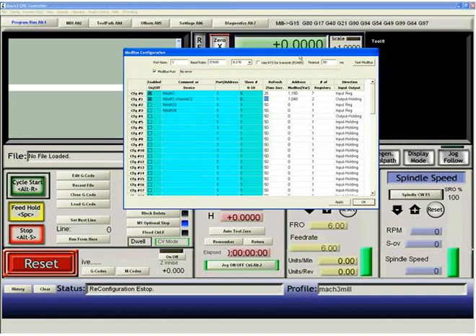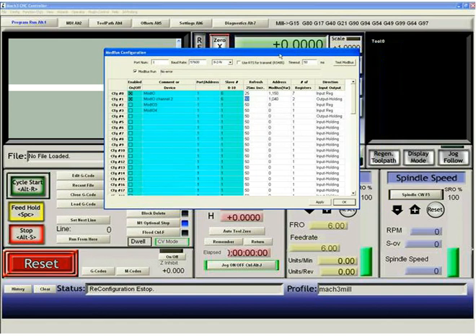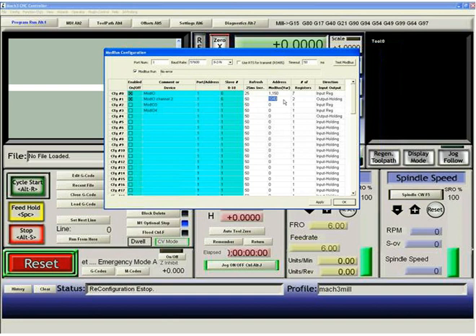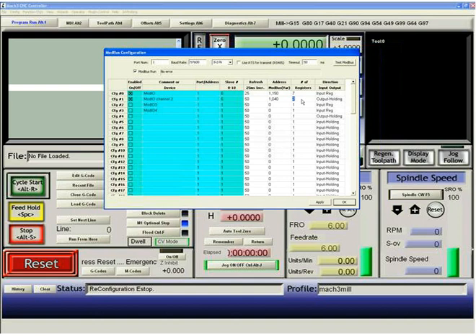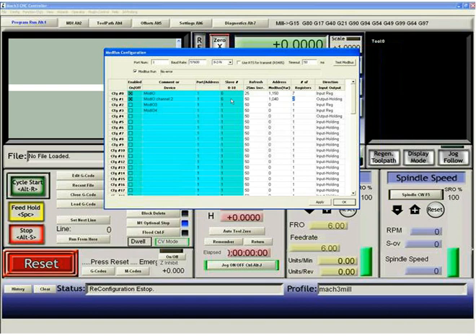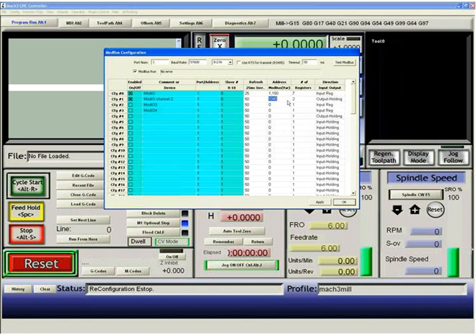And you can see, if you could read this anyway, you can see that what I've told it to do is starting at address 1040 in the Modbus, fill it with two registers. So it's going to take the first two registers from configuration 1 and send them into the Modbus starting at address 1040.